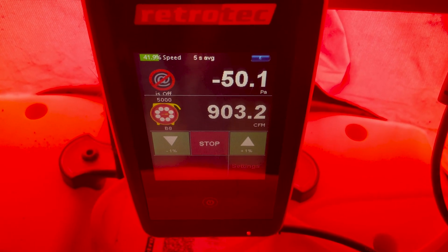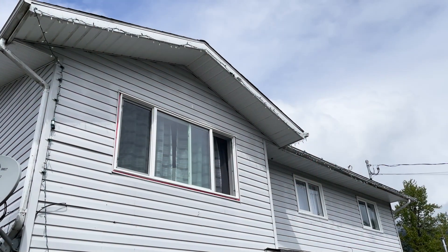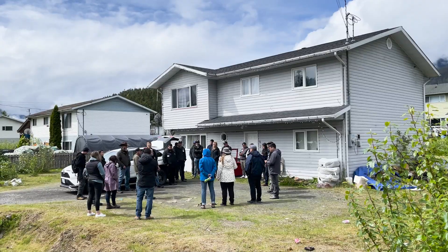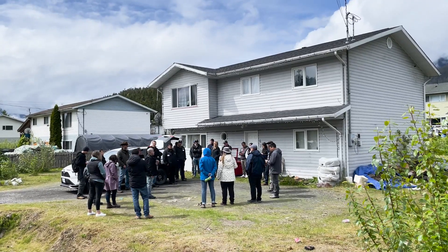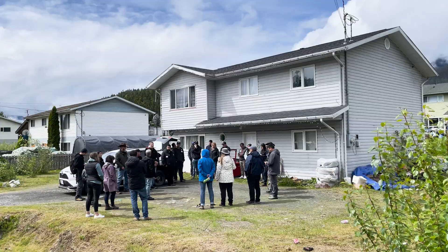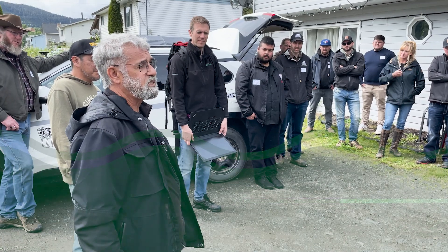The temperature is uneven. We have a massive stack effect happening up there. Downstairs is condensing — you can see it where it's turning into mold. There is a ventilation issue, generally speaking. So all these things we'll talk about in more detail tomorrow and what we can do to fix them up.